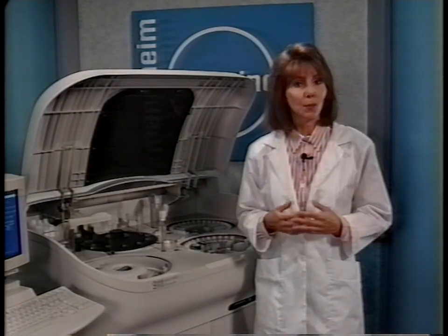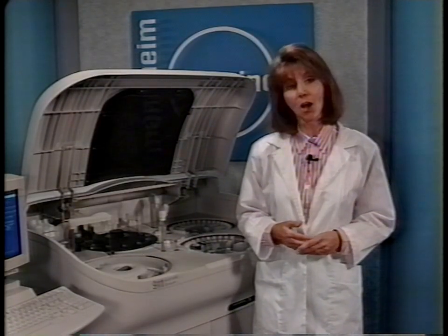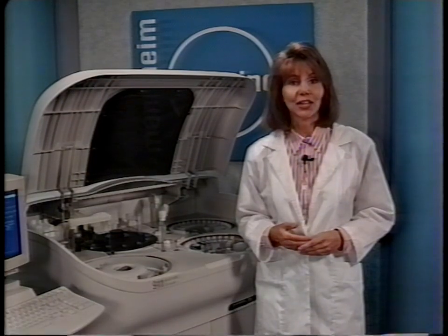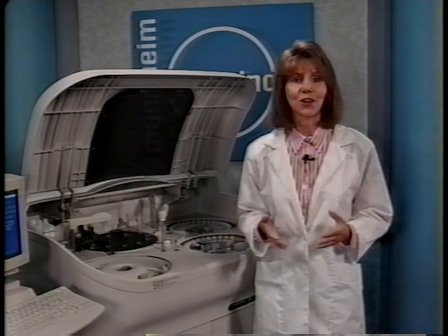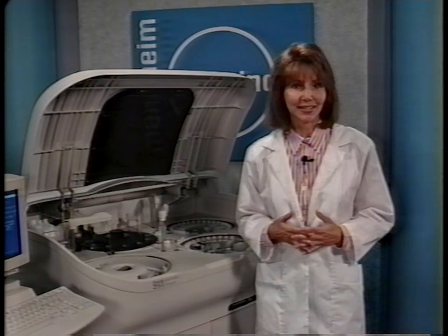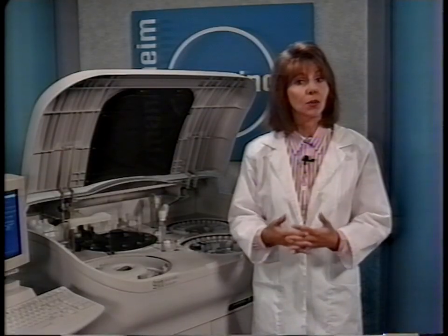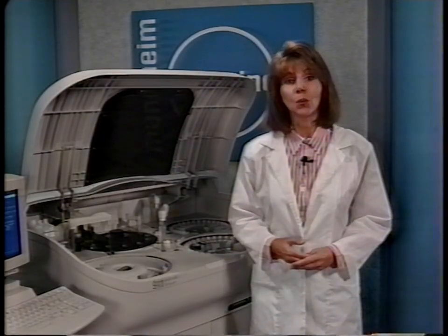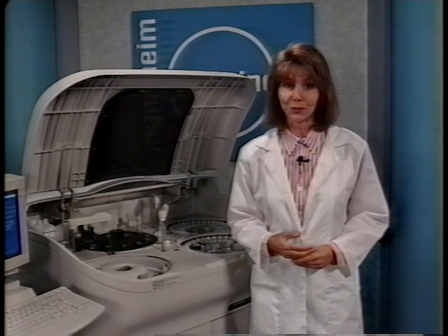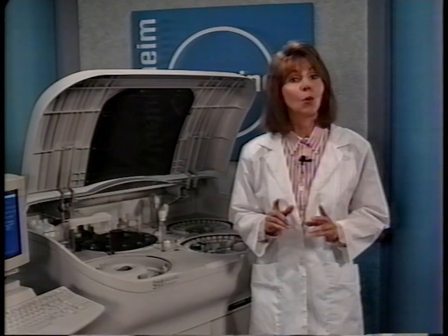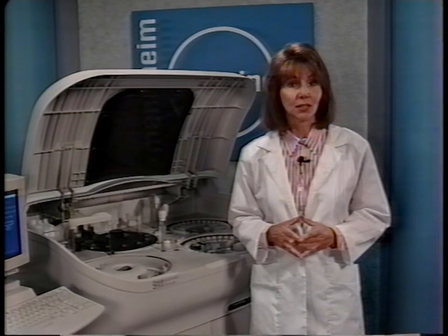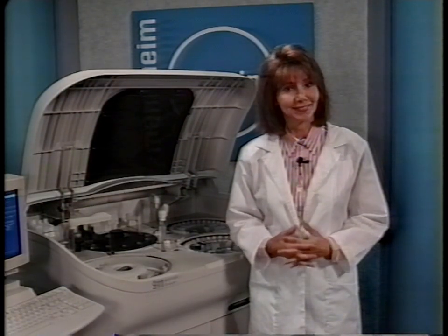Reagent bottles are barcoded, allowing random placement on the 911. Reagents can go into any position as long as they are on the appropriate disc. If a reagent bottle is on the wrong reagent disc, the system will mask or inactivate that chemistry. You can also place more than 1 bottle of a reagent on a disc for tests that are run frequently.